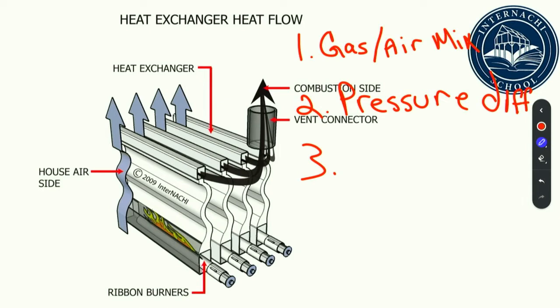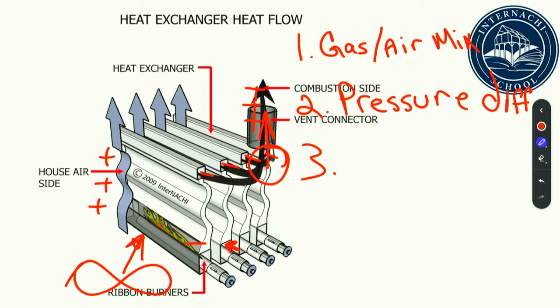And I'm going to go in a little bit more on that. So if I have my inducer fan up here, and that's going to be blowing air upwards, I'm going to have, and just for a short bit, because it's still hot air on the mid efficiencies, but I'm going to have positive air pressure after the fan, and I'm going to have a negative air pressure before the fan. So inside the heat exchanger, it's going to be negative pressures, right? Then I'm going to put a blower fan that's going to blow air on the outside, and that's going to create a positive pressure on the outside of this heat exchanger. So let's say I did have a hole in this thing, then air is actually going to flow into the heat exchanger as opposed to carbon monoxide coming out of it.